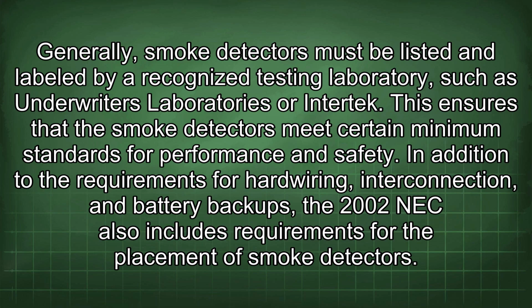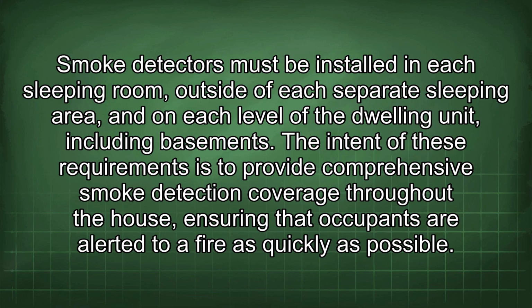In addition to the requirements for hardwiring, interconnection, and battery backups, the 2002 NEC also includes requirements for the placement of smoke detectors. Smoke detectors must be installed in each sleeping room, outside of each separate sleeping area, and on each level of the dwelling unit, including basements. The intent of these requirements is to provide comprehensive smoke detection coverage throughout the house, ensuring that occupants are alerted to a fire as quickly as possible.